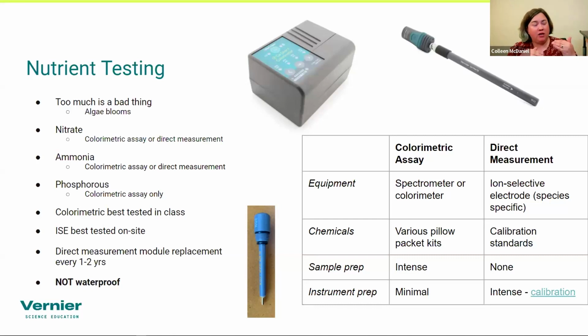Phosphorus, there's only a colorimetric assay available. There is not an ion specific electrode for those. And the way I kind of look at these is when you're doing nutrient testing, colorimetric is going to be a lot easier to do in class because of having to use a colorimeter or spectrophotometer. You want a more controlled environment than being outside. ISEs, best to use them on site. What's great is you can get them calibrated and set up beforehand, and then just have them ready to go out when you go into the field and do an instant test when you're out there.